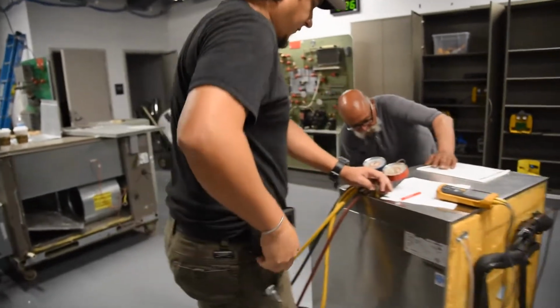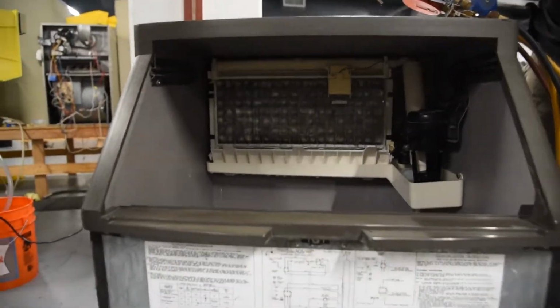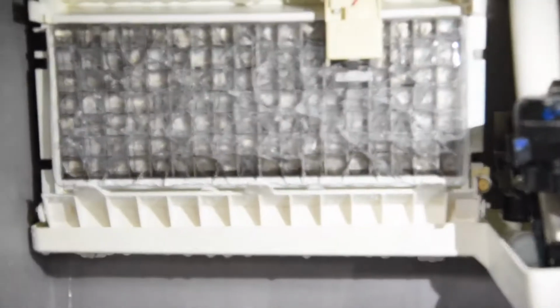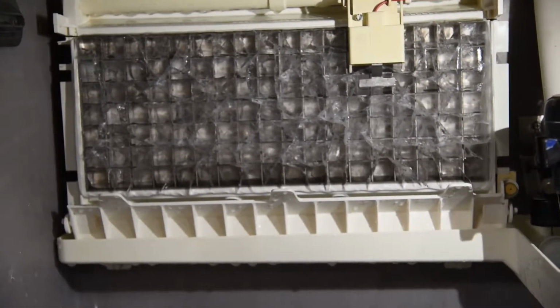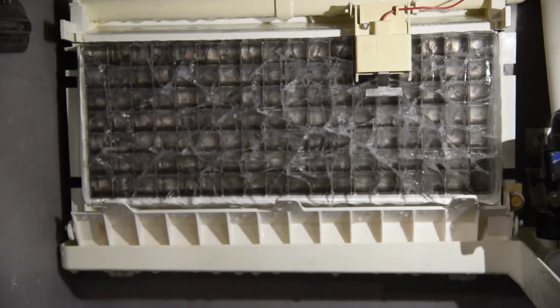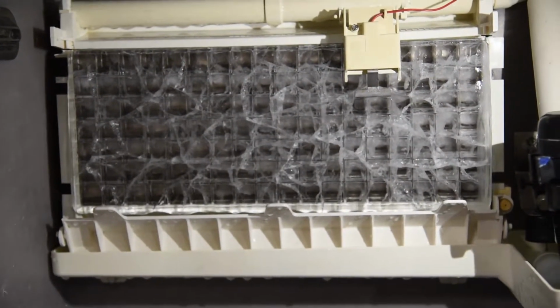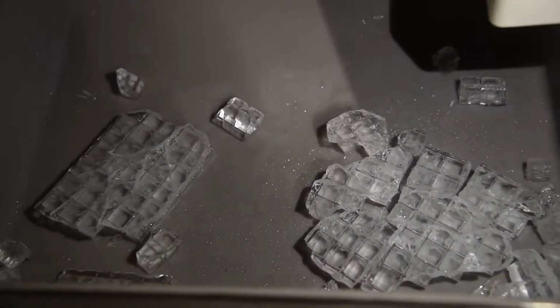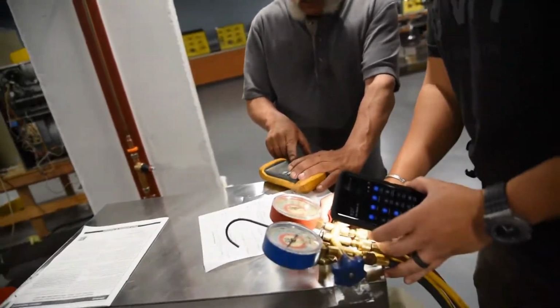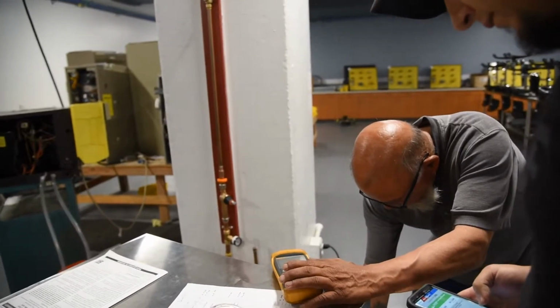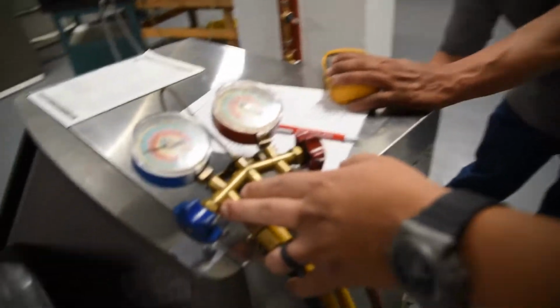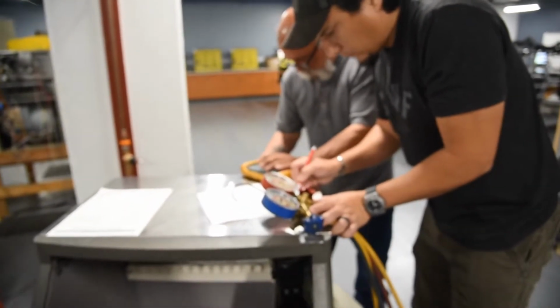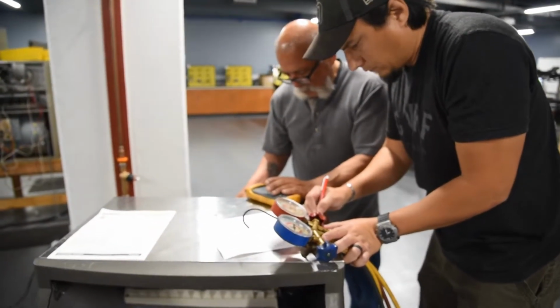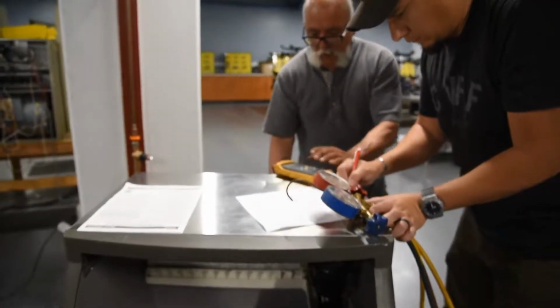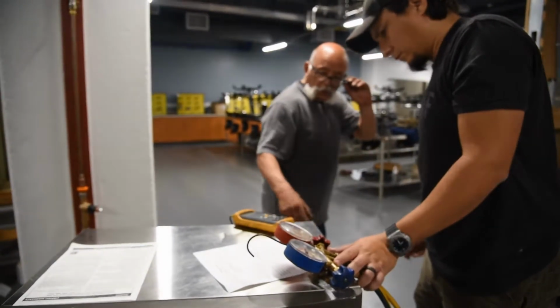It's getting ready to fall. See it coming out? Yeah. Okay, now what it'll do is go back into cooling. See how the temperature's changed? Okay. Now the hot gas bypass is deactivated? Hot gas tubing is 80 degrees. And the liquid line is 84 degrees.